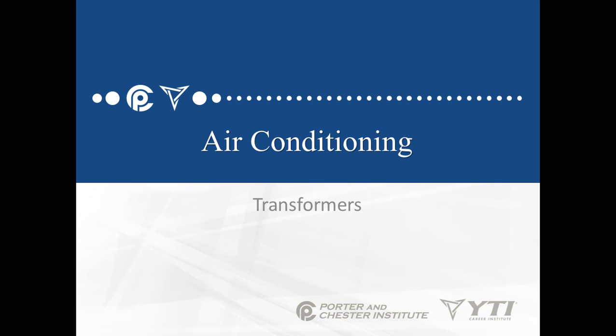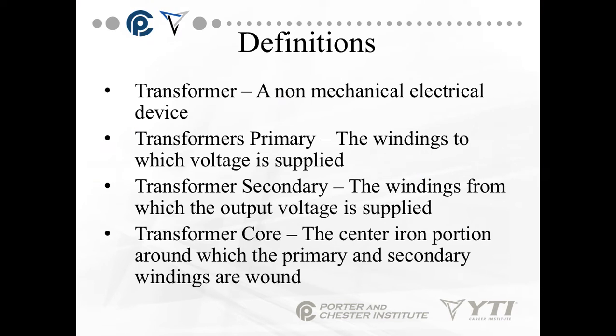In this lesson, we're going to be talking about transformers and how they work in your air conditioning systems. Now, remember, we have line voltage, which comes in an air conditioning system most often at 240 volts or the air handler at 120 volts. So we have to do something with this to make it safe and usable in a low voltage application so that there's no chance of shocking hazard or anything else, and could put it into control voltage.